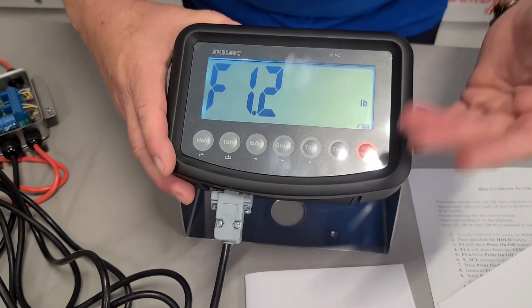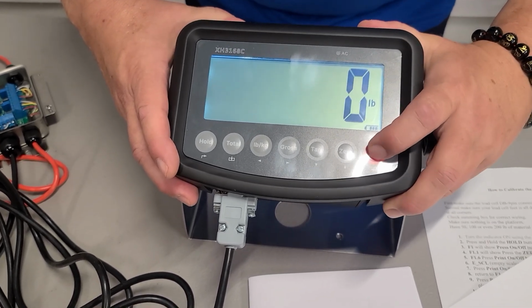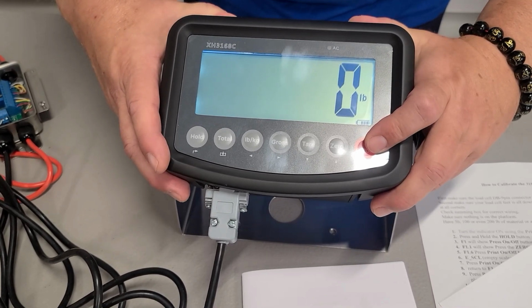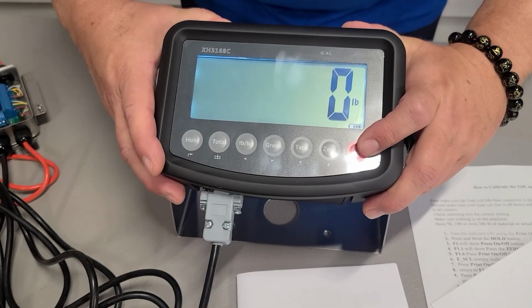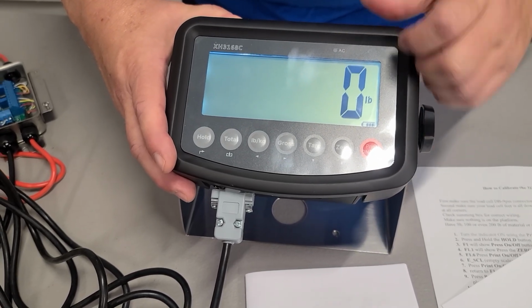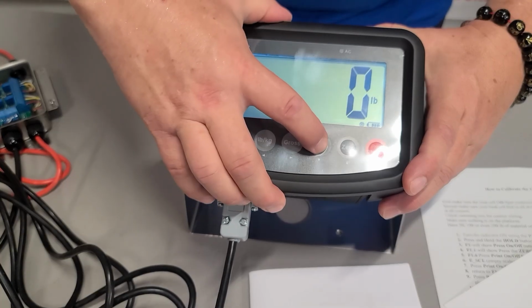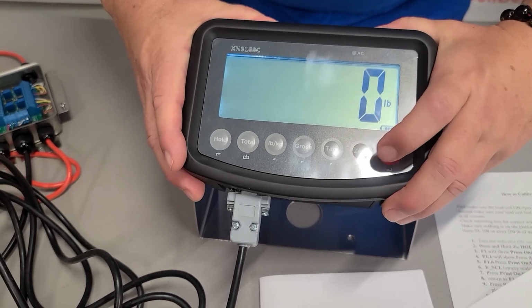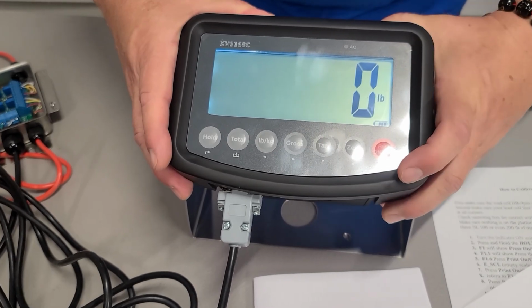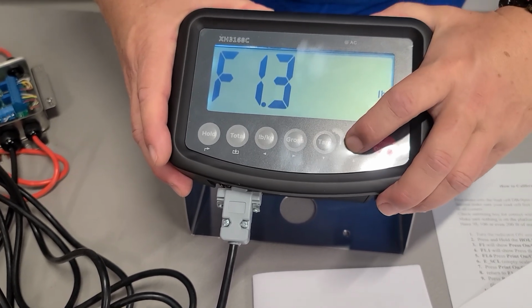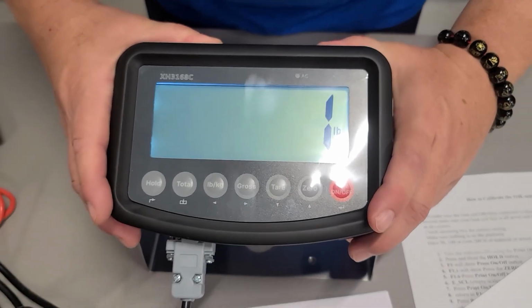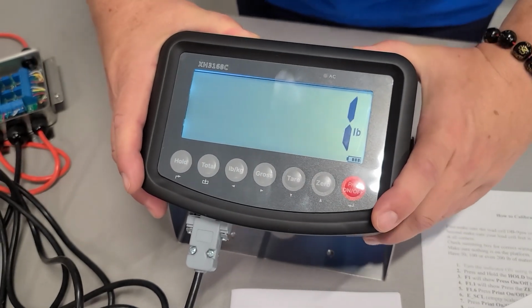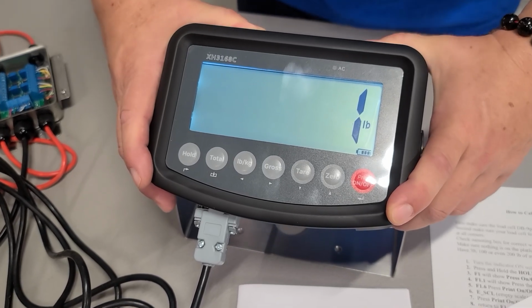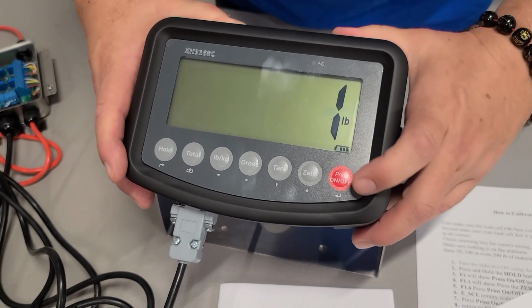F2 is going to be your number of decimal places. So if you are counting by 1 pound, you have no decimal place, so it stands for 0. If you want to change that, you can by pressing the up and down arrow, which tells you where your decimal place is going to be. Next is going to be F3, which is your count by, your division. That means the indicator will count by 1 pound at a time. So when you put 1 pound on it, it'll count by 1 pound.